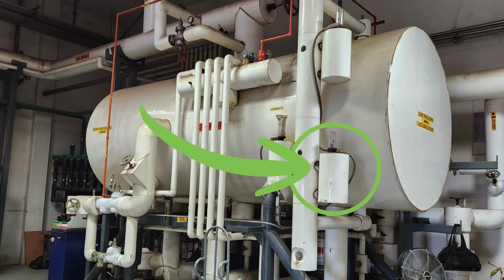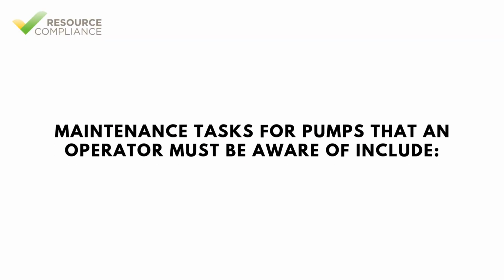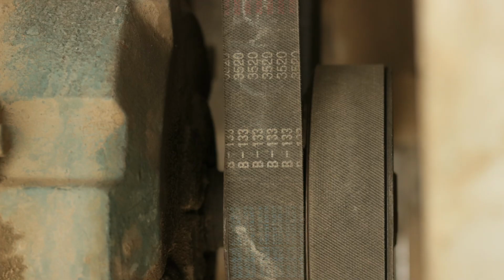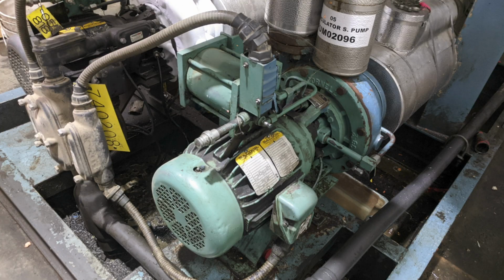Pumps installed on a recirculator package will be interlocked to cut out if the liquid level in the supplying vessel drops too low. Annually, the low liquid level or cavitation cutout must be tested. Maintenance tasks for pumps that an operator must be aware of include replacing belts and lubricating motor bearings.